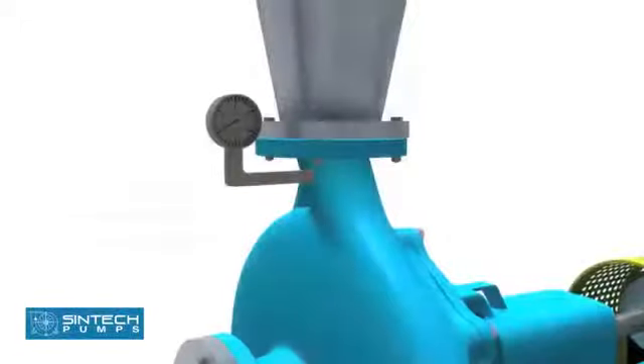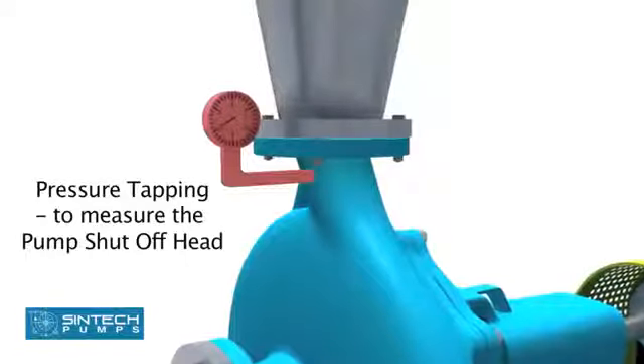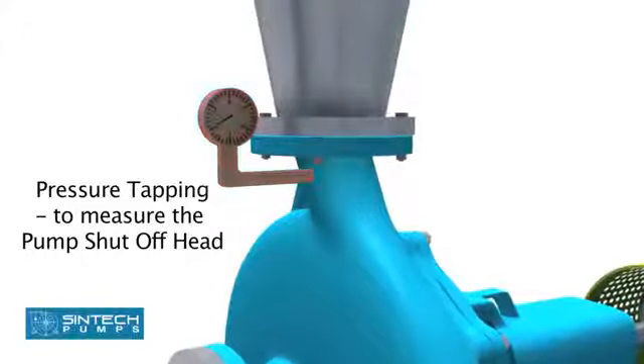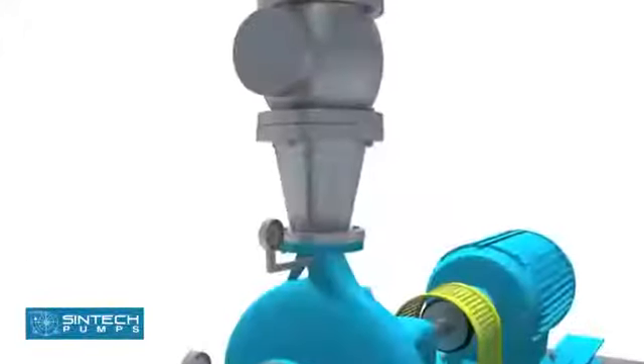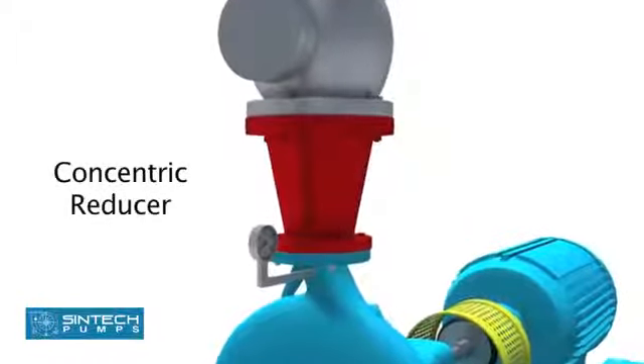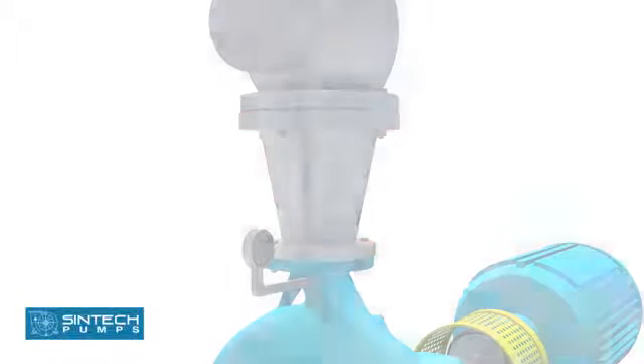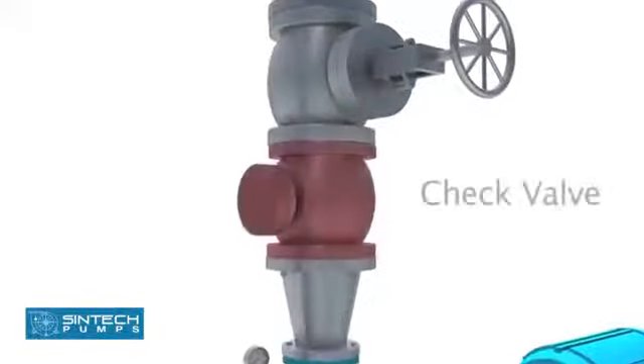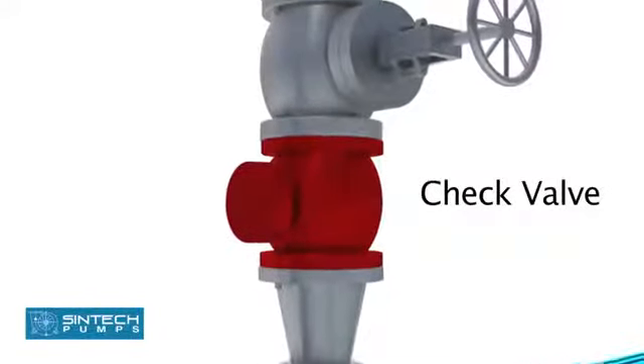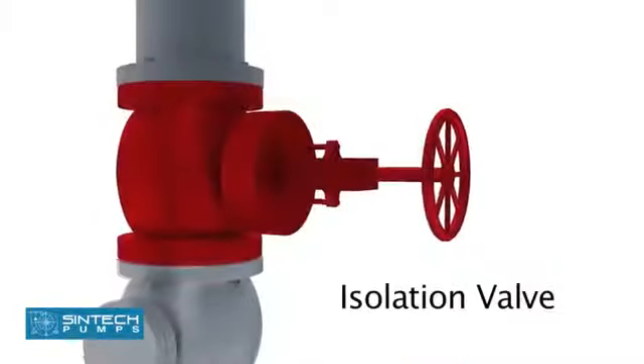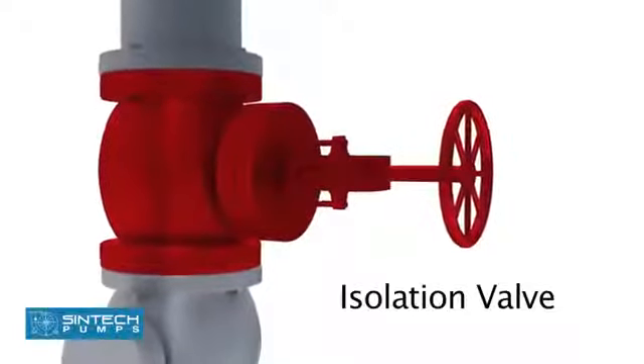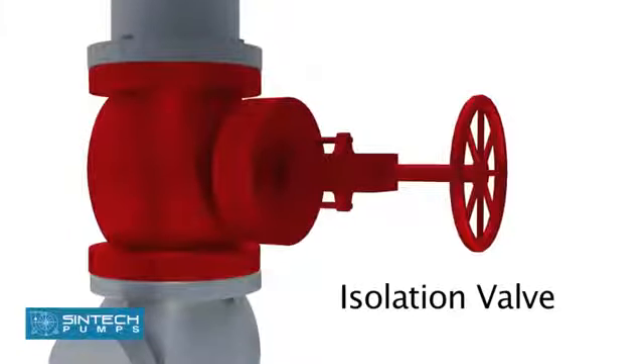Description of the discharge pipe: There should be a pressure tapping as close to the pump outlet and before the isolation valve as possible to measure the pump shut-off head. Concentric reducers are installed in the discharge pipe to minimize friction losses. The check valve used should be of non-slam type to prevent hydraulic shocks. The isolation valve is provided downstream of the check valve so these can be taken up for servicing whenever required.